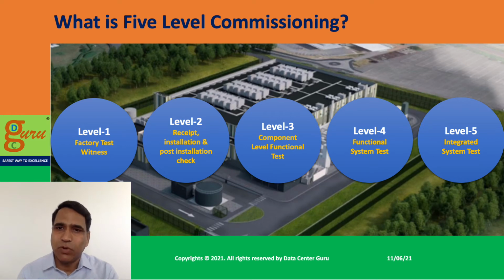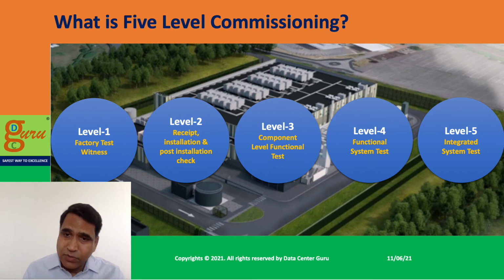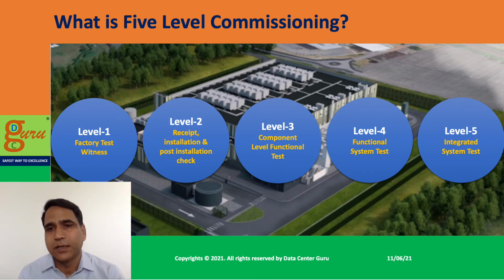Finally, we talk about integrated system tests. A data center is an integrated system consisting of multiple systems, the building blocks I talked about. So you put in an IT rack, put a dummy load of equivalent capacity, switch it on, and do the entire integrated test to check whether all the building blocks in the data center are working in coordination, in an integration mode, and are able to provide the desired performance and reliability or redundancy. There is a detailed level of scripts for this.